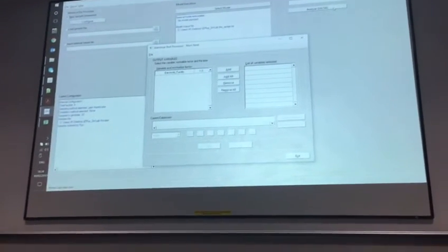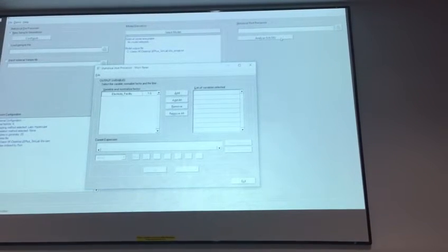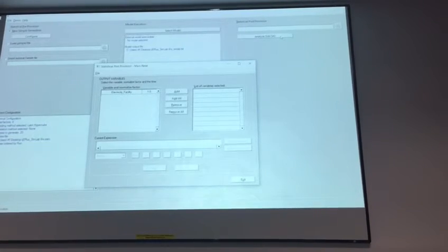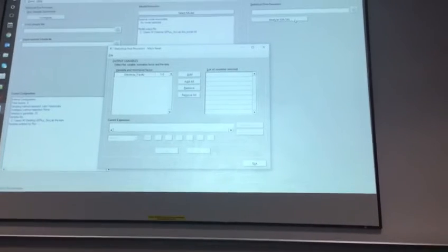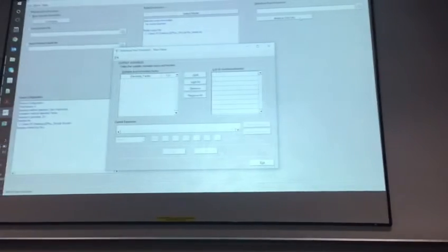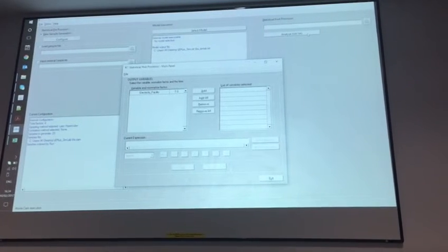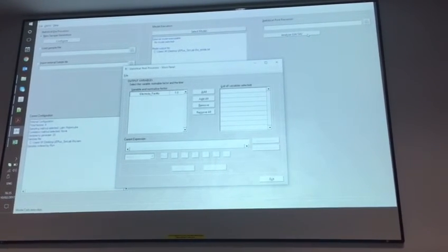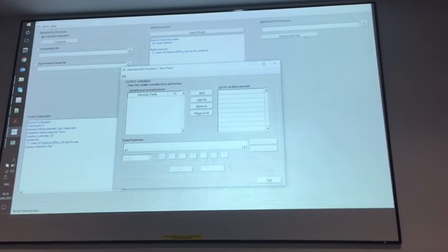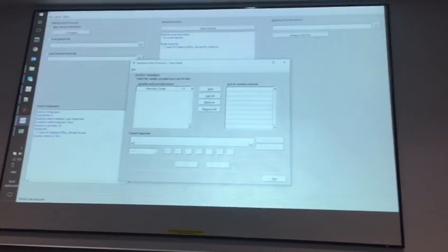So depending on the outputs we want to assess our inputs against, we are choosing a set of parameters. If we are analyzing the gas consumption in the house, heating set point is very important if it is heated by a boiler. If we are analyzing only electricity consumption, then heating set point is not that important. It will probably not be important at all, but lighting intensity might be important. So depending on the outputs, we are choosing a set of input parameters to conduct any parametric sensitivity or uncertainty analysis.